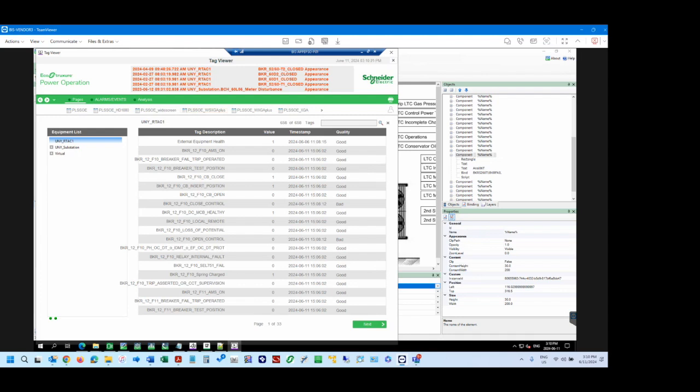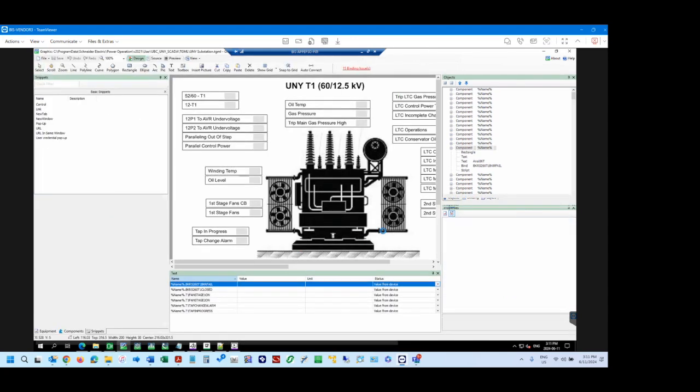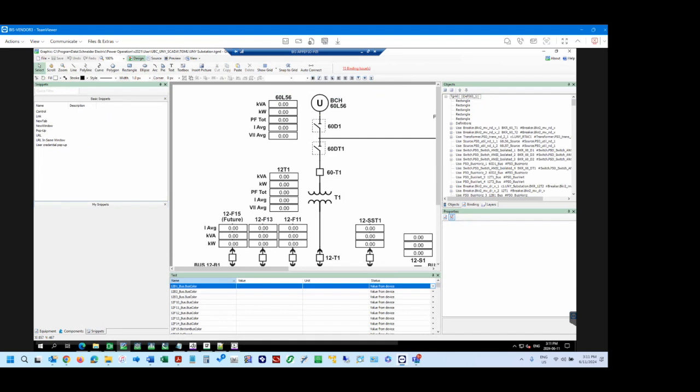What would you mean by configuration data? In the past, I used an EMS system, an energy management system, done by GE, and one of the functionalities of that system was that it had a study mode. That was basically an offline mode that would take a snapshot of the real-time system, including the configuration at the transmission level. It basically would be like a screenshot of the system at any given time, and then you can do contingency analysis or any kind of study you wanted, like a power flow study.